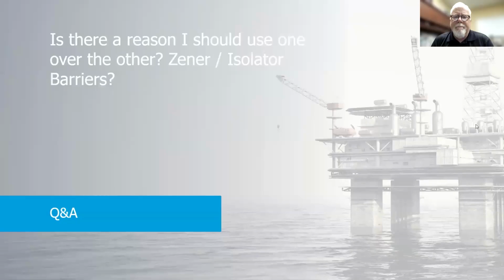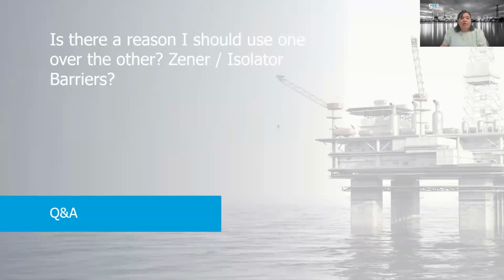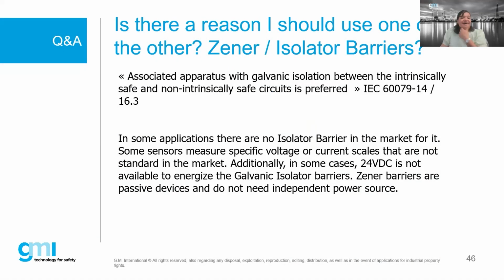Is there a reason I should use one over the other? I found on the standard there is this one sentence: an associated apparatus with a galvanic isolator between the intrinsically safe and non-intrinsically safe circuits is preferred. However, as Bob was mentioning, both are associated apparatus, both are allowed per the standard to be utilized, both will give you the intrinsic safety protection in the field. It really depends on your application and some of the challenges you might have in that specific area where you're installing the system.